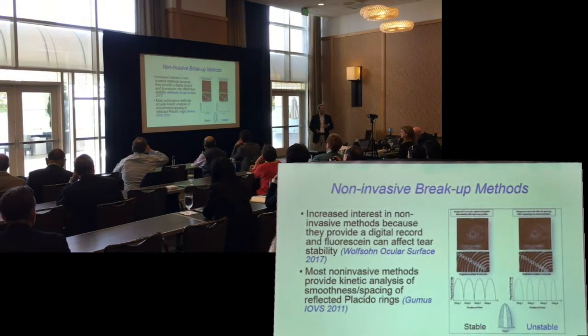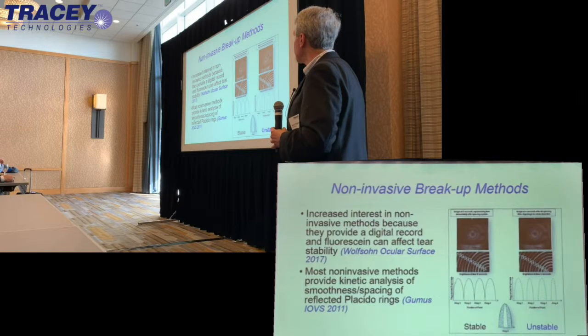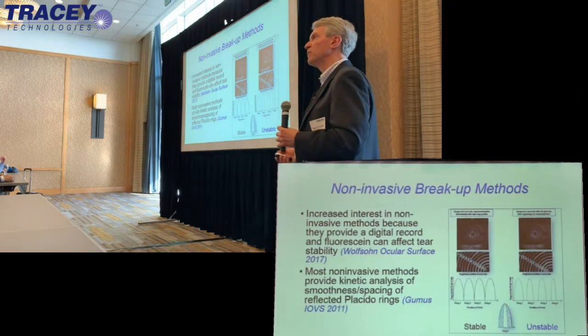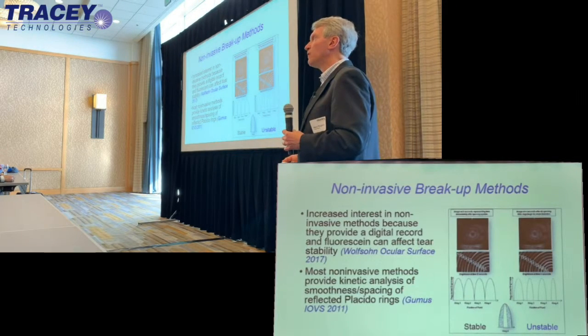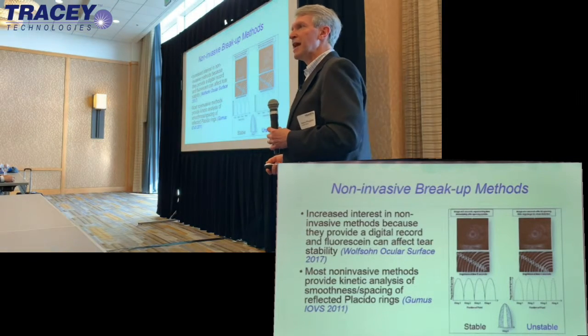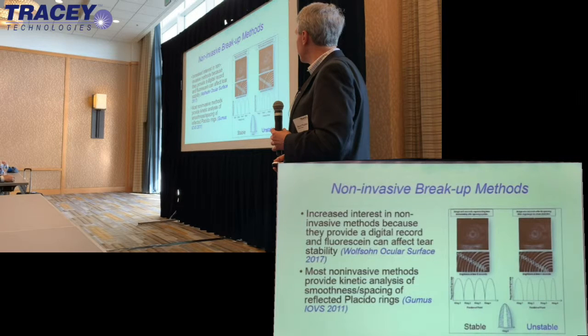But I think there's more and more interest in using non-invasive tear breakup time methods because they provide a digital record which you can go back and look at, and maybe try to identify the underlying problem. Like if the patient has corneal fibrosis or epithelial basement membrane disease, you can actually go back and see consistently where the tears are breaking up in that area.